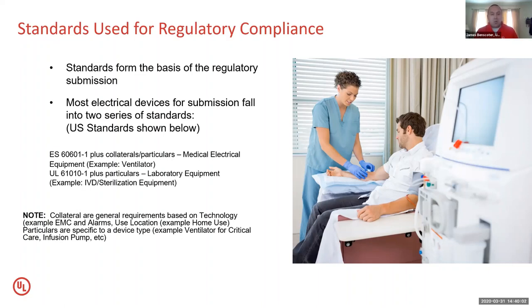Now, when you notice, when I say the word particular and collaterals, particulars, the best way to think about it is very specific requirements for a specific device. So when we're talking about ventilators, for example, the 601 series of standards actually has three different categories of ventilators, whether they be critical care, that's one type, or where they go into the next step and they go into the home use ventilators that may, depending upon the level of breathing that the patient needs, will fall into two other buckets.